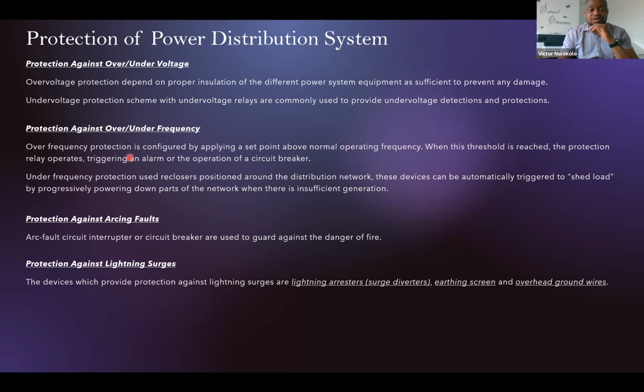Protection against under and over frequency. This happens where we have a sudden drop in load or a sudden drop in generation. If we have a sudden drop in load, we have a surge in the power system because the demand suddenly drops, so the supply becomes surplus and the frequency varies. The opposite is also the case where we have a sudden drop in generation. Maybe you have 3 generators, and all of a sudden one drops. That means you lose a section of your load.